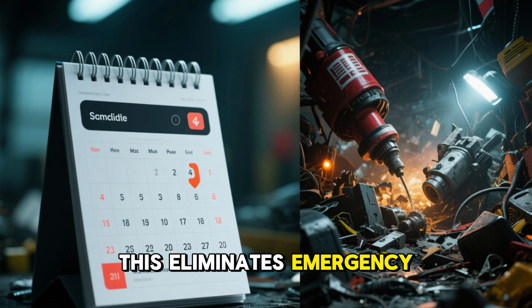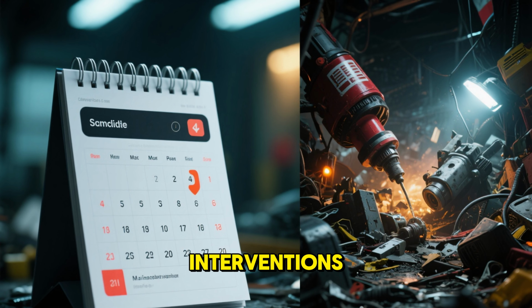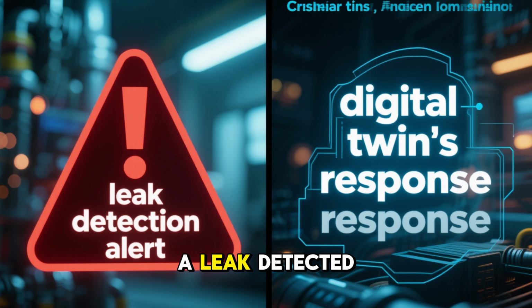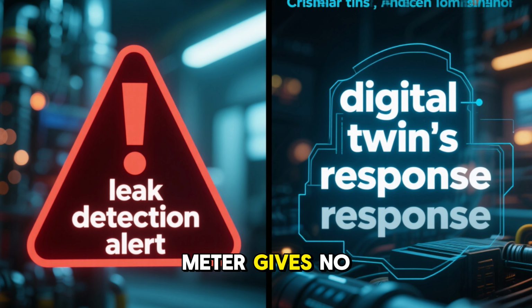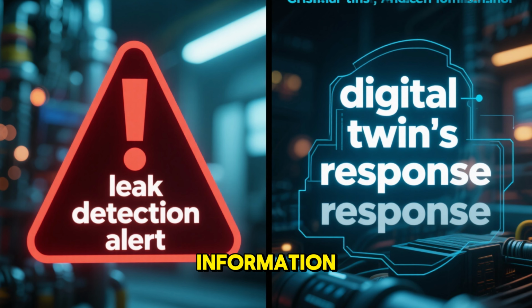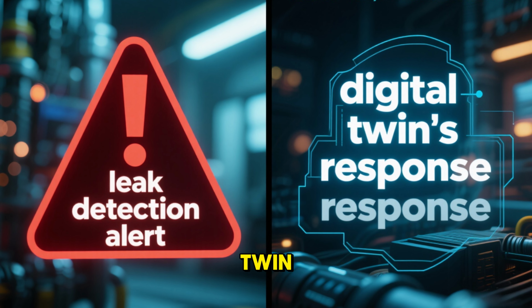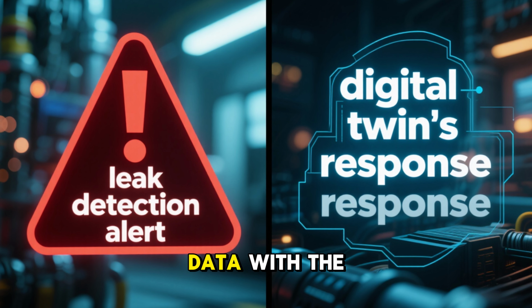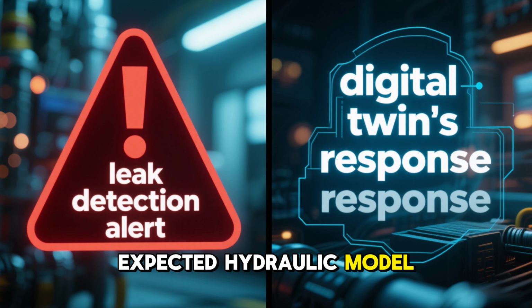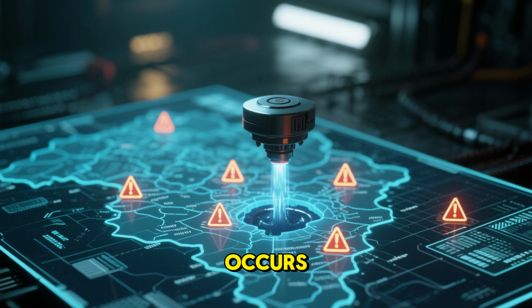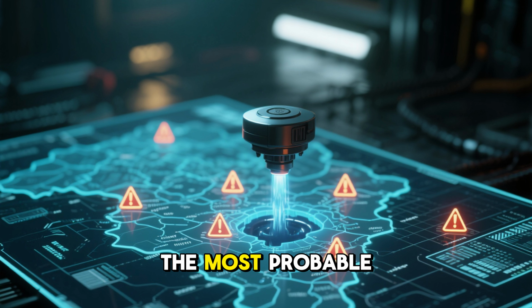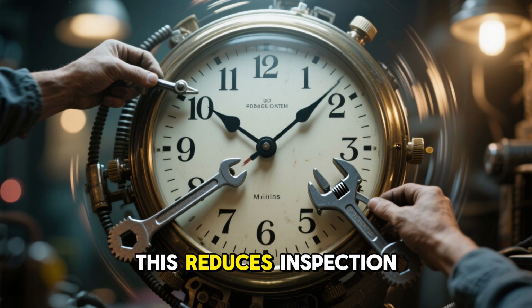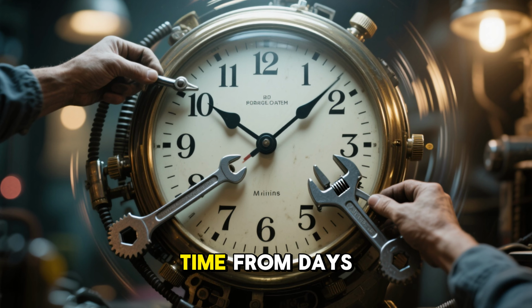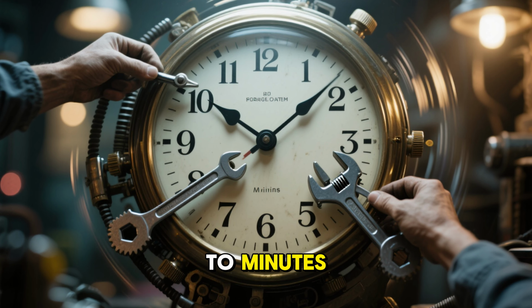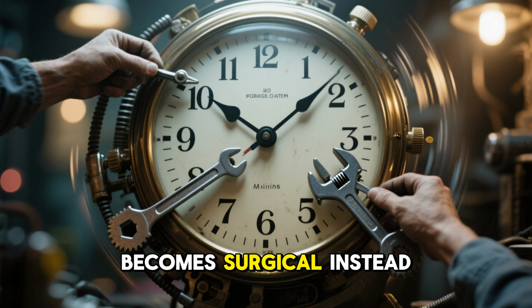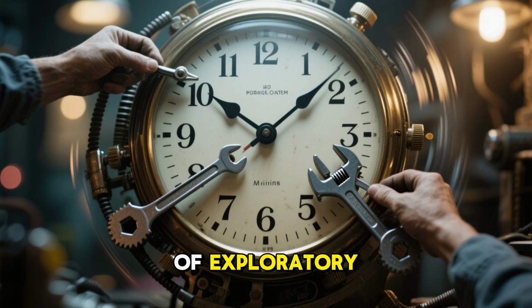This eliminates emergency interventions. In large buildings, a leak detected at the main meter gives no location information, but a digital twin compares real sensor data with the expected hydraulic model. When a deviation occurs, the system calculates the most probable location. This reduces inspection time from days to minutes. Maintenance becomes surgical instead of exploratory.